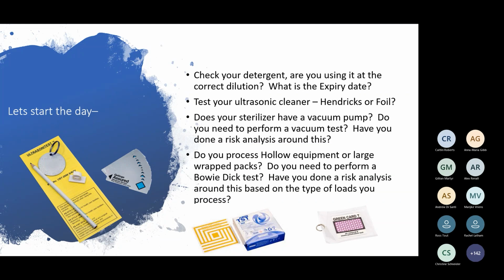And also you need to have the capability of the machine from the manufacturer. So MELAG will often say that the 23VSs won't pass a green card test. So there's no point in even doing a green card test in a machine if the manufacturer is telling you that it's not going to pass. So you need to know the instructions for use from your manufacturer and look up what your machine is capable of and test your machine based on those.